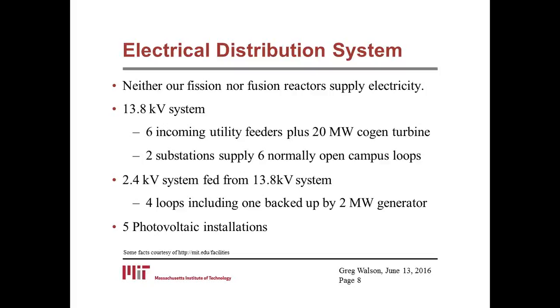And then you'd dump the whole bus when you - you're talking about islanding? Well, suppose on your bus you've got more load than your generator is going to pick up, and you lose the utility. Right now the way our system unfortunately is set up, if we lost the utility and the campus load was greater than what the turbine could take, we would go black.